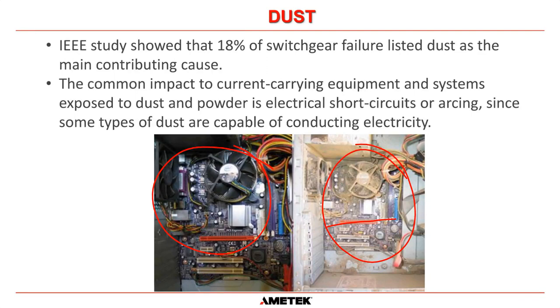And when it's cleaned off, this is what it should look like. And we don't know what's inside dust. Dust could have some kind of powder or substance in it that is conductive, or that dust could become moist with humidity and that could become conductive. But basically what dust allows is for short circuits or arcing between two components. It's not supposed to happen. And that will cause failure of a control board or a switch, and would be a very bad day for everybody.